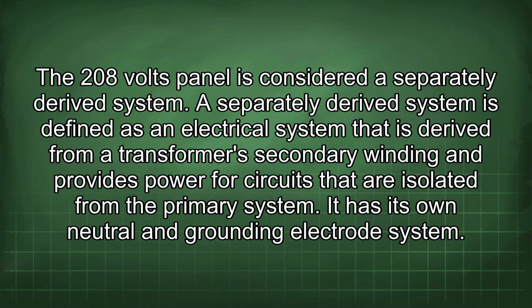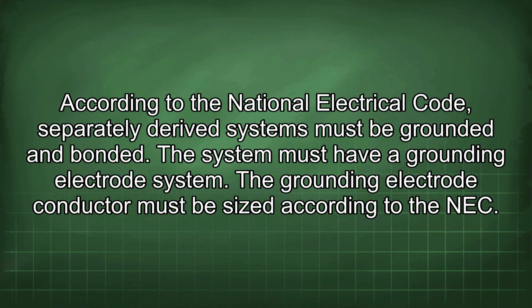208 volts panel is considered a separately derived system. A separately derived system is defined as an electrical system that is derived from a transformer's secondary winding and provides power for circuits that are isolated from the primary system. It has its own neutral and grounding electrode system. According to the National Electrical Code, separately derived systems must be grounded and bonded.